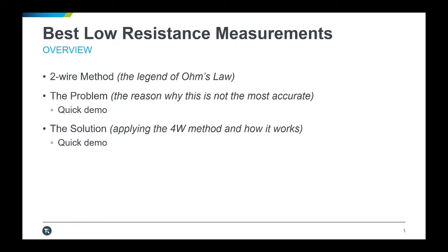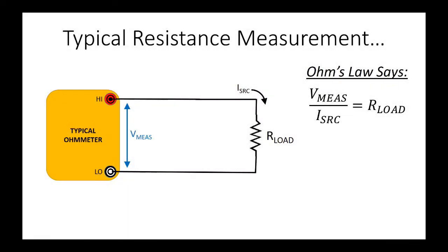The resistance function of your typical ohmmeter or multimeter will source a known current to your device under test (the resistor) and perform a voltage measurement at the terminals where the test leads are inserted. The resistance value is calculated using the sourced current and measured voltage values. When your resistance values are greater than 100 ohms, this is probably fine.